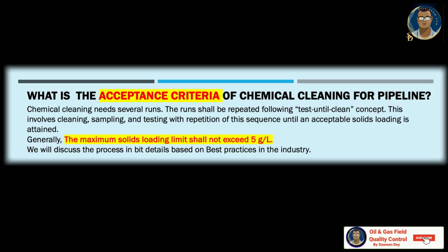What is the acceptance criteria for chemical cleaning of pipeline? Chemical cleaning needs several runs. The runs shall be repeated following the test until clean. This involves cleaning, sampling and testing, with repetition of this sequence until an acceptable solids loading is attained. Generally, the maximum solids loading limit shall not exceed 5 grams per liter. We will discuss the process in a bit more detail based on best practices in the industry.